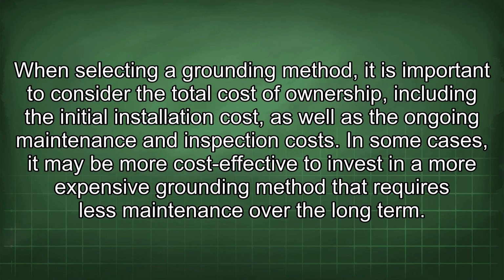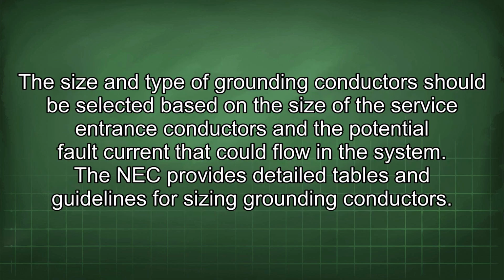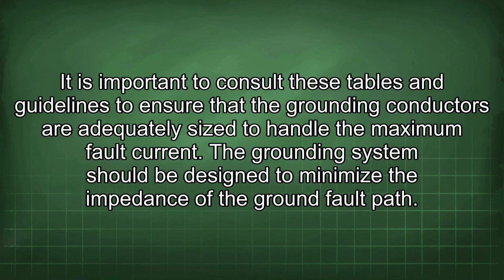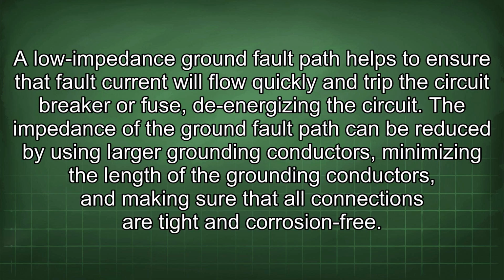over the long term. The size and type of grounding conductors should be selected based on the size of the service entrance conductors and the potential fault current that could flow in the system. The NEC provides detailed tables and guidelines for sizing grounding conductors. It is important to consult these tables and guidelines to ensure that the grounding conductors are adequately sized to handle the maximum fault current. The grounding system should be designed to minimize the impedance of the ground fault path. A low impedance ground fault path helps to ensure that fault current will flow quickly and trip the circuit breaker or fuse, de-energizing the circuit.